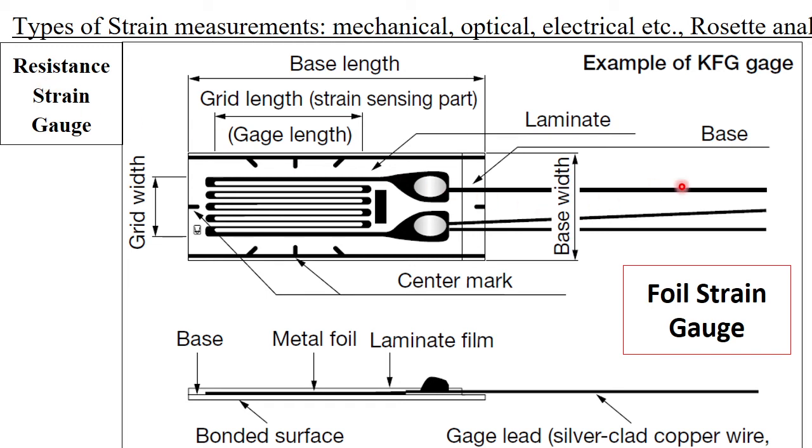Here, this goes to the transmission line. You see these wires. This is the sensor unit. The basic sensor unit is shown here. This is known as the strain gauge, a foil type strain gauge; the details we will discuss afterwards. So this is the base width, and here we have a base length. This length and width part is our basic measurement unit, where we have some locations for soldering wire. And these wires go into the measurement unit.